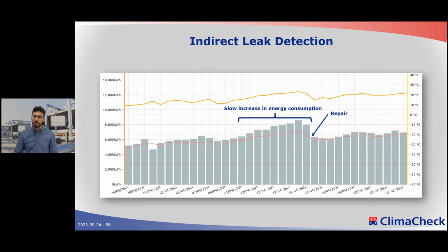This is a third example, also using the energy signature, the predicted energy. And in this case, we see a gradual increase of the energy consumption. At this point, we have an issue with a leak. So refrigerant leakage, and this has been fixed, and the energy consumption goes back to what was predicted. Again, it's important to continuously monitor even optimized systems. Most of the time, systems are commissioned, but they still work in a non-optimized way. But even if they're optimized, problems will occur.